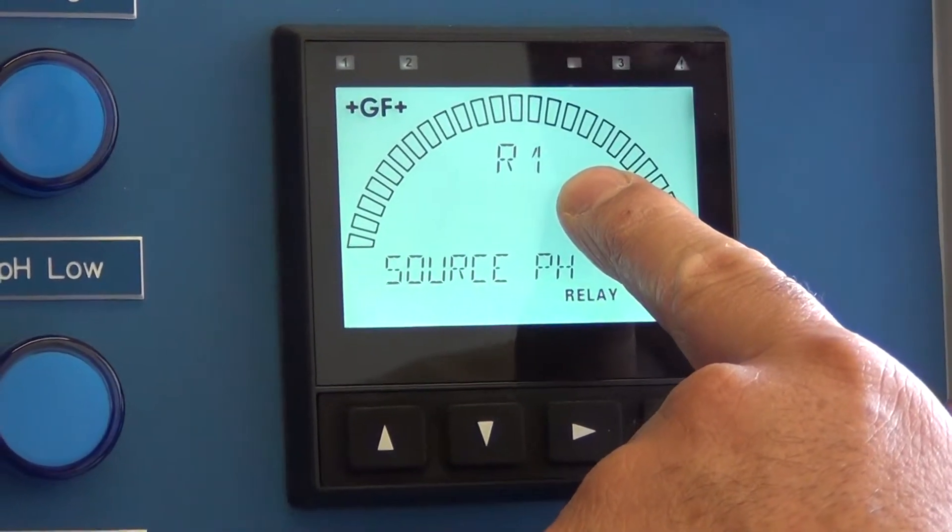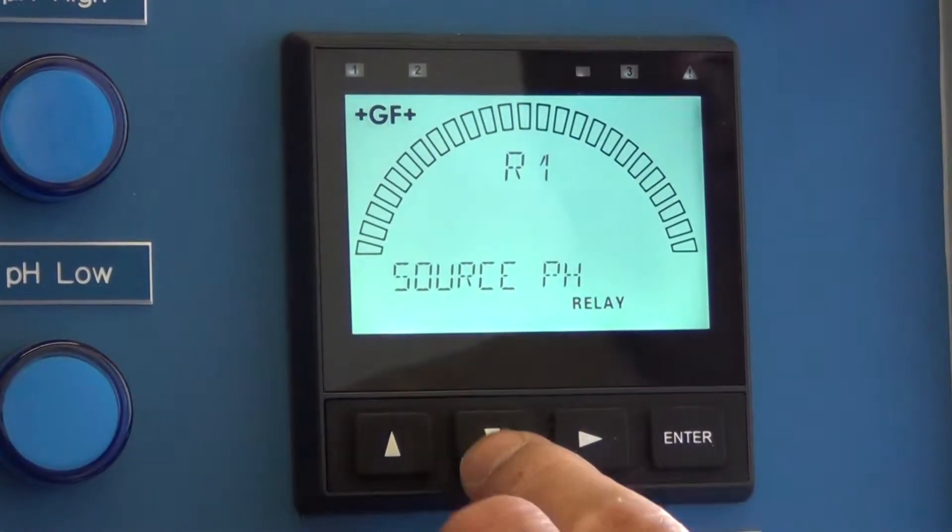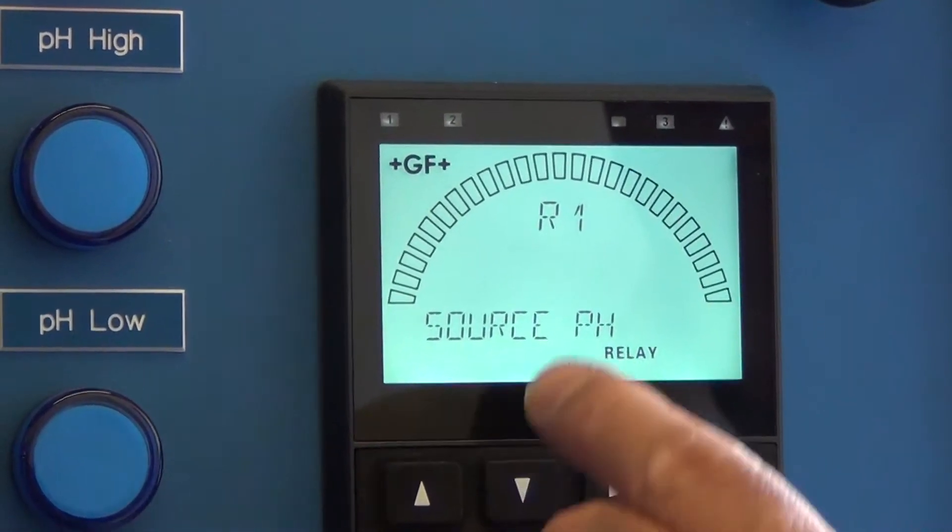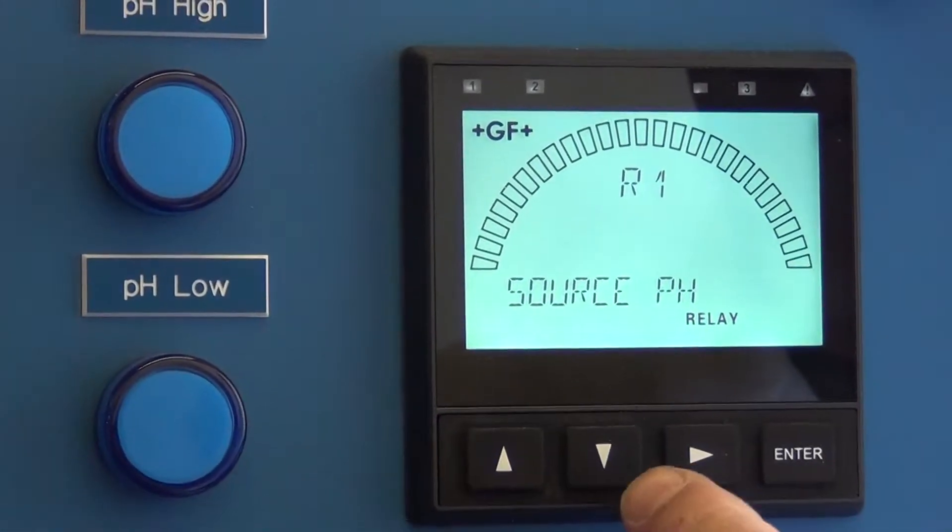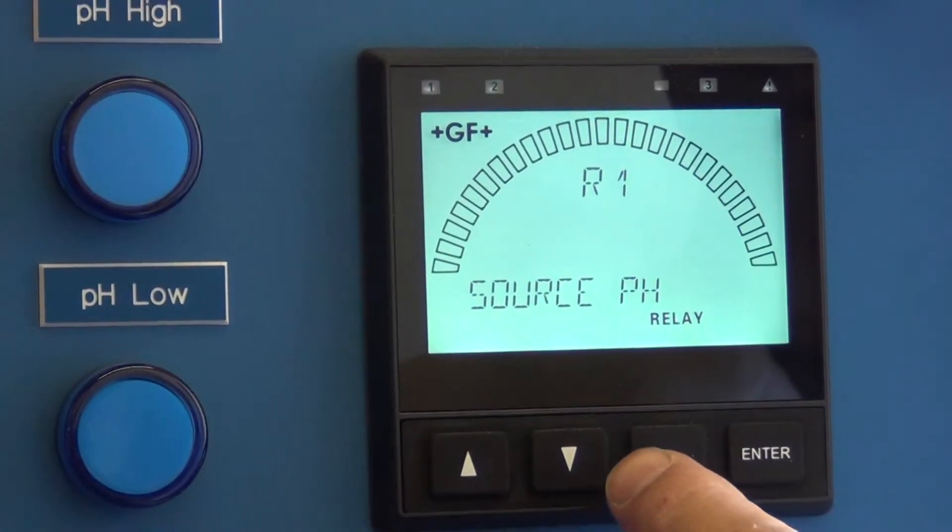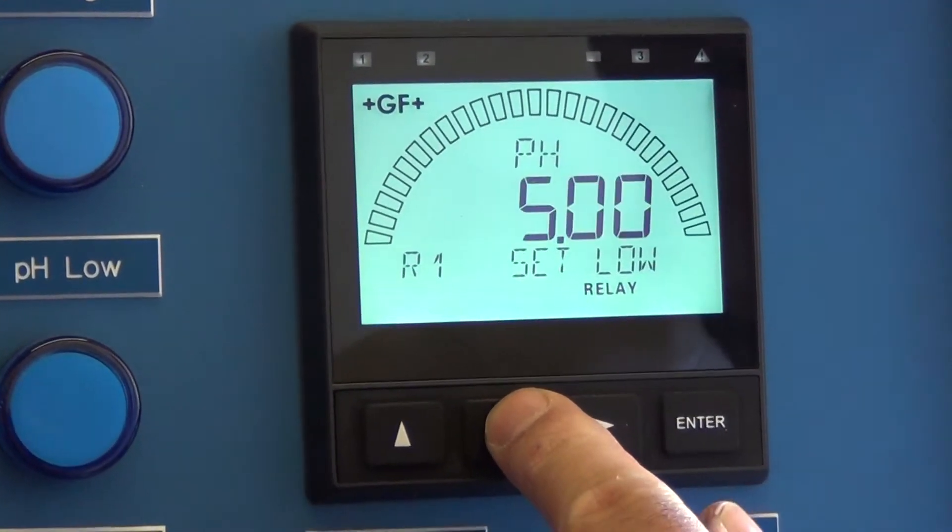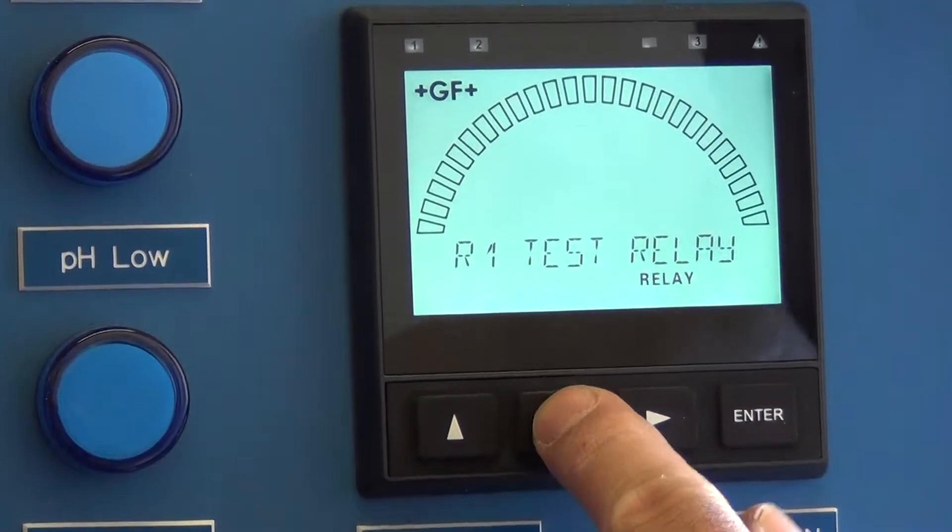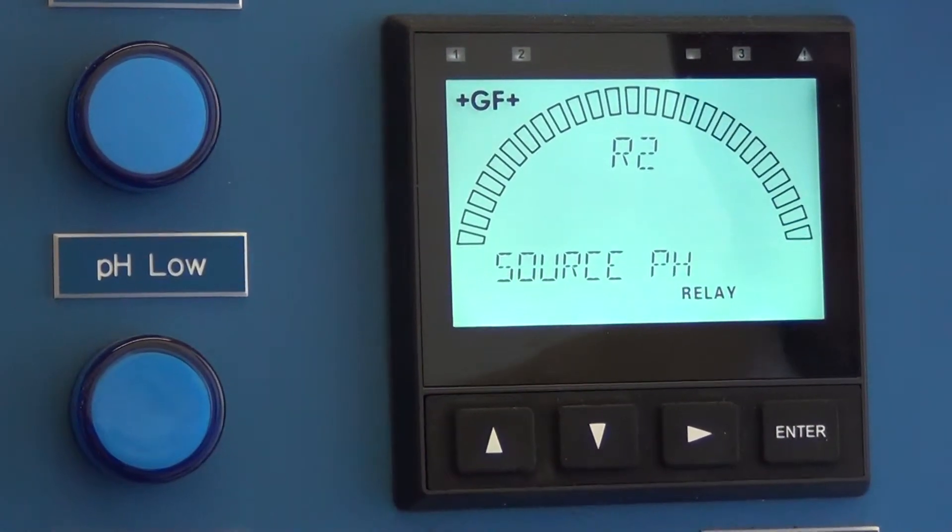R1 is the pH operating window. That's what sets your pH alarm when you're outside of R1's operating parameters. It alarms. We want to go to R2. R2 is the relay that controls the acid pump.